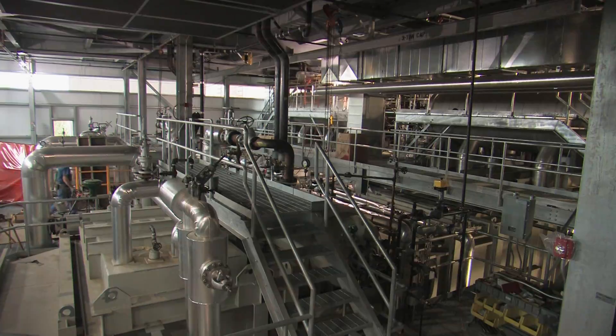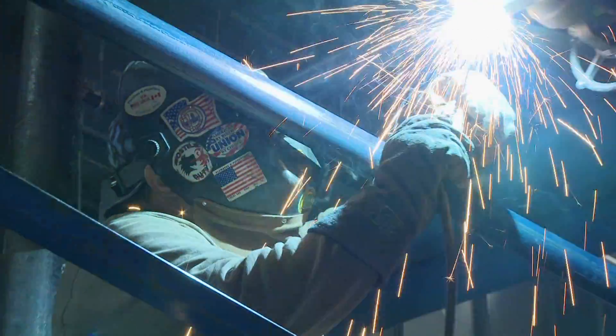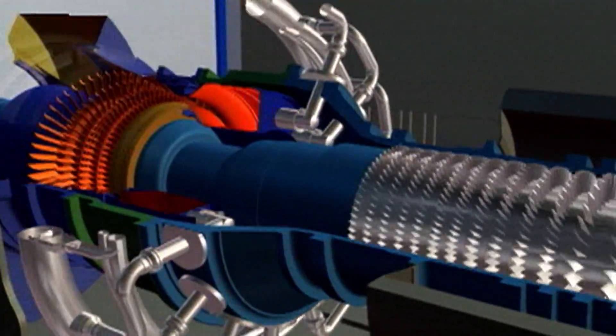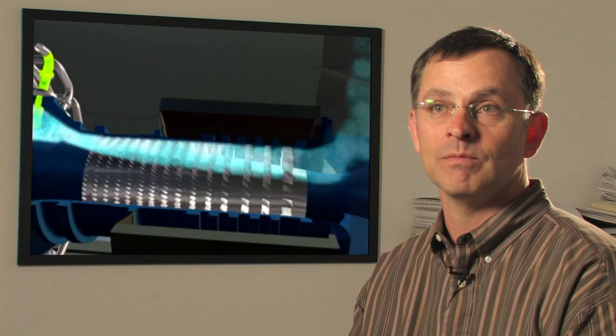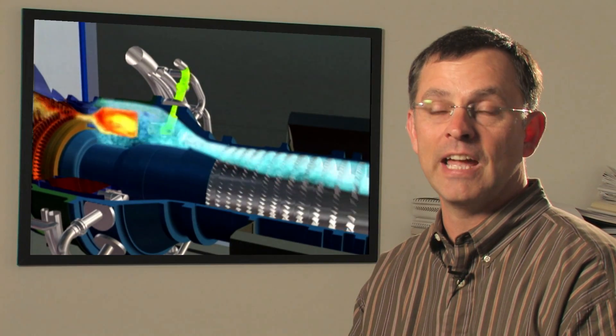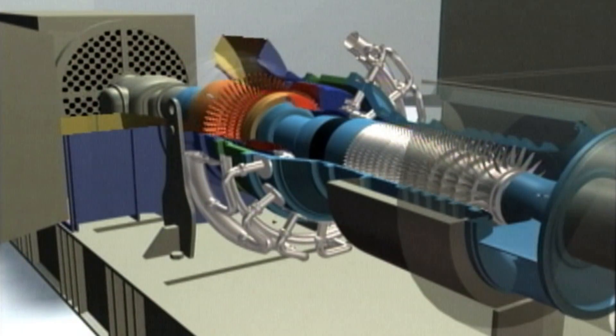The Cornell co-gen plant was a complex problem that required the use of union labor at all stops. Co-generation is simply taking one type of fuel and creating two kinds of energy out of it. Natural gas enters the facility at high pressure. It is injected into the combustors of our Brayton Cycle combustion turbines, which are designed to produce electricity, generating electricity at about 15 megawatts each.